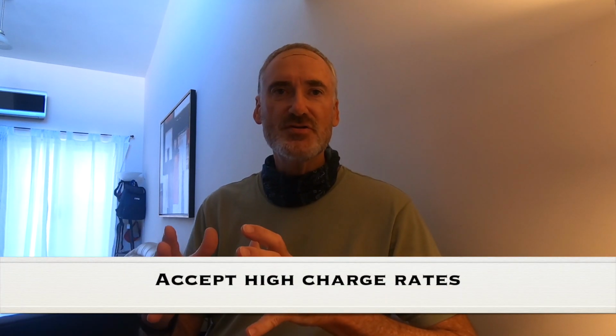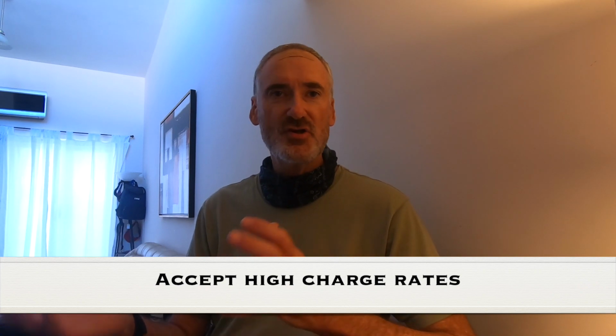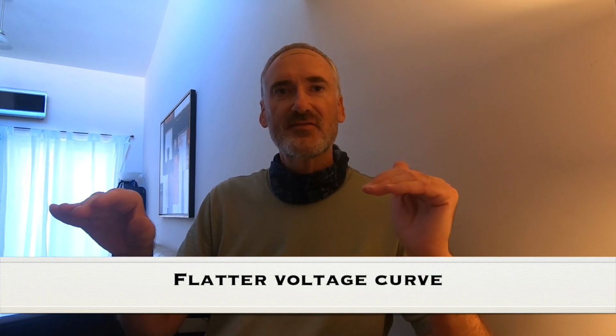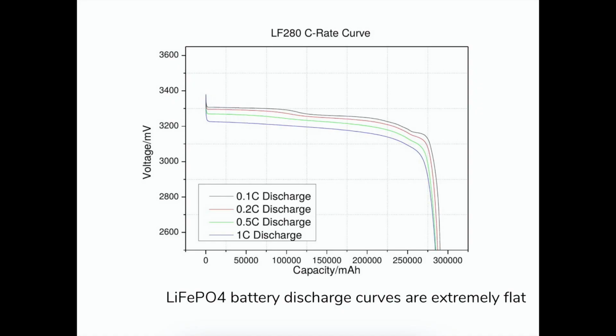The third reason is that they can accept a lot of charge, which means when we're charging the batteries with our generator, we don't have to run it as long because they'll charge up faster. The fourth reason is they have a much flatter voltage curve as capacity is used. Lead acid batteries' voltage drops pretty steadily as capacity is drawn down, but lithium iron phosphate batteries are pretty much flat, which makes the electronics very happy—the pumps, electronic devices, lights, everything works better with these batteries.